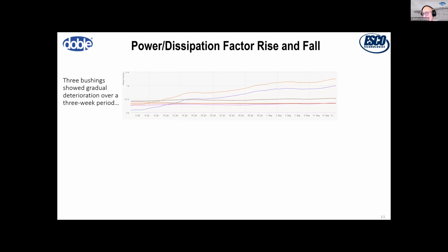Here's another cautionary tale about bringing this data into your model. In this case, three bushings were being monitored, and on this graph we're plotting not only the zero sum power factor - essentially adding them all together to get a relative version - but also the true power factor. Here we can see both the sum current and the relative value rising together, which helps confirm that it is in fact that one bushing, and not a combination of bushings.